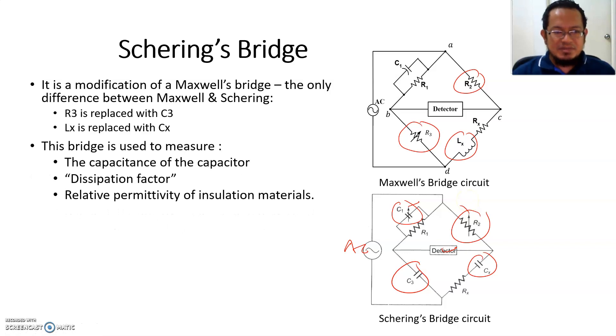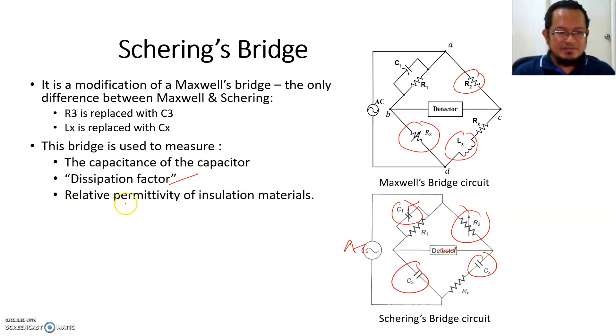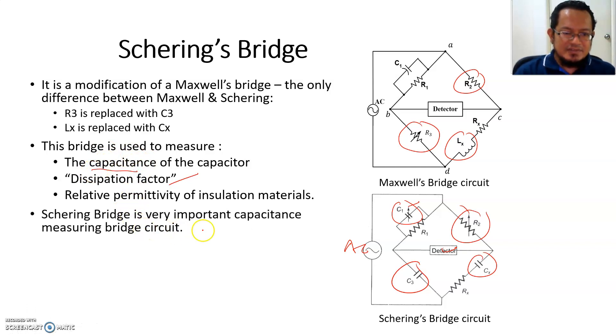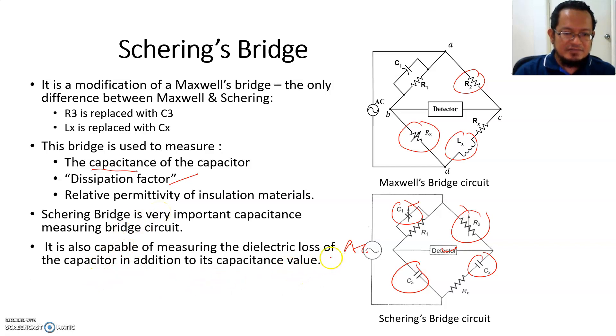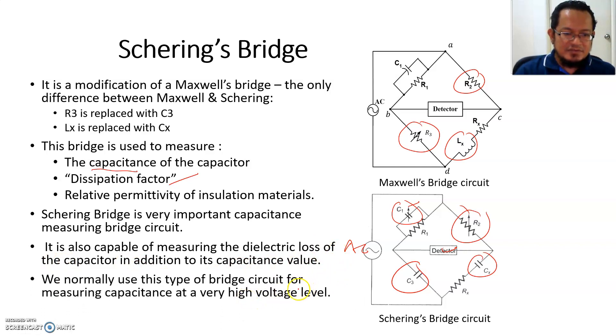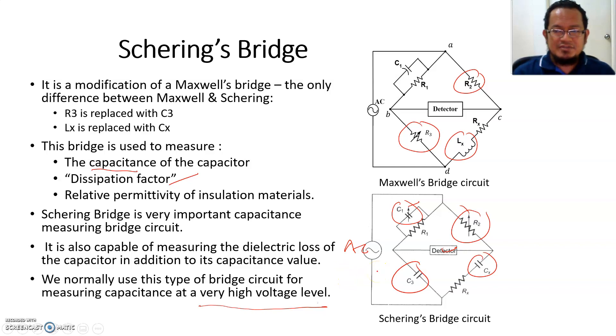This bridge is used to measure mainly the capacitance of the capacitor, dissipation factor, as well as relative permittivity of insulation material. That's just another property of material — we're not going to talk a lot about this today, just the capacitance measurement. The Schering bridge is a very important capacitance measuring bridge. It is also capable of measuring the dielectric loss of a capacitor in addition to its capacitance value. We normally use this type of bridge for measuring capacitance at very high voltage levels — those taking high voltage power systems may have learned this.